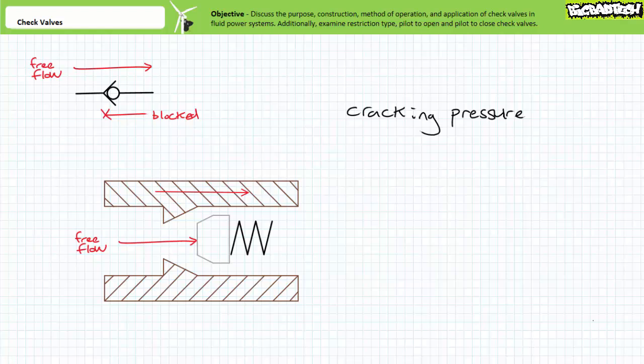Most check valves have extremely low cracking pressures on the order of 5 psi. At the full open pressure, the poppet fully unseats and allows unrestricted flow. The region between cracking pressure and full open pressure would see increasing flow in the free flow direction as the poppet progressively unseats.